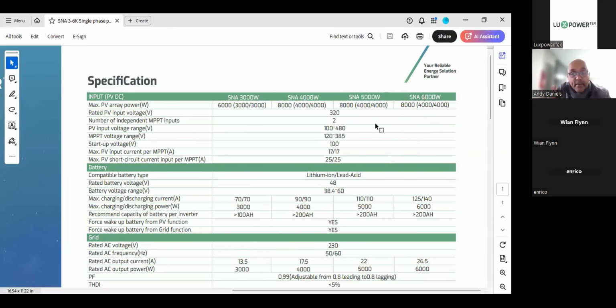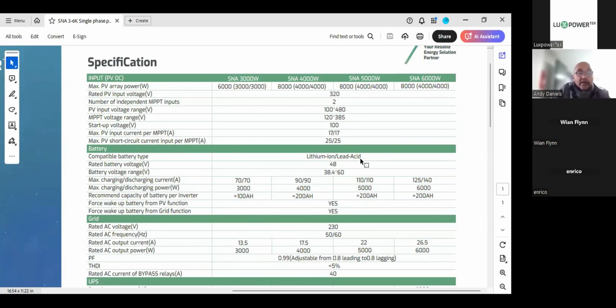Always remember that solar panels are temperature dependent. Their yield is temperature dependent. So if you have a bright, clear day, like we will definitely get now in winter, and the temperature has dropped, if you get a temperature drop either with cold wind blowing over the panels or the ambient temperature because it's been snowing or there's a cold wind in the air and the temperature of the panels drops, then the yield will increase. This is why there are limitations here, that we cannot exceed these, okay? Very, very important. Otherwise, you will end up damaging your panels. We do have a 25 amp maximum short circuit current, but the critical thing here is short circuit, okay? It's not load, it's short circuit for a very, very short period of time. We've seen some MPPTs come in here looking like they've been in a house fire.